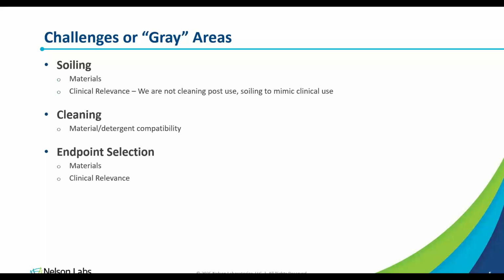And with cytotoxicity, if your device is patient contacting, it would be critical to assess the detergent residuals, and cytotoxicity is just one method that does have an acceptance criteria associated with it. But there are other methods out there as well to assess detergent residuals, but it is something you'll want to do. You're taking your device through this cleaning process and then it gets used on a patient. And we want to ensure that there's nothing harmful remaining on the device from the cleaning that could impact the patient.